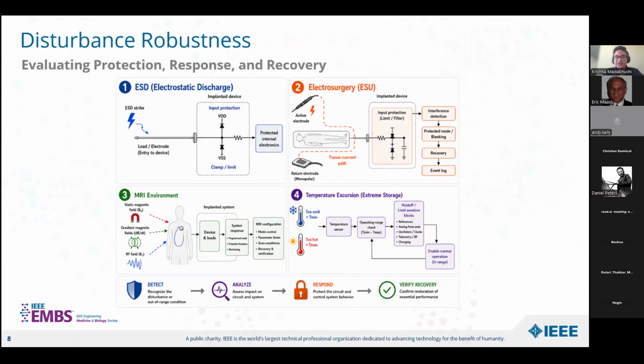And then there is electrosurgery, which creates a different challenge. It creates high frequency energy that can couple into our sensing paths. The system may need not only protection here, but also filtering, blanking, a controlled operating mode, and verification that normal behavior returns after the event occurs. And then we have a most common problem, magnetic resonance, MRI exposure. It's much broader than the other two because the complete implanted system may experience static magnetic fields, gradients, and RF energy. So compatibility depends on the device, leads, operating configuration, and a lot more.